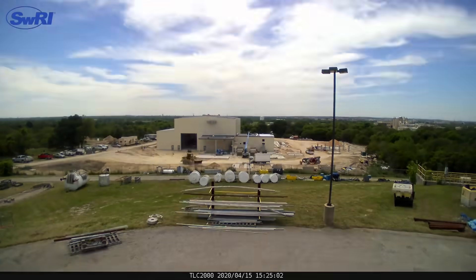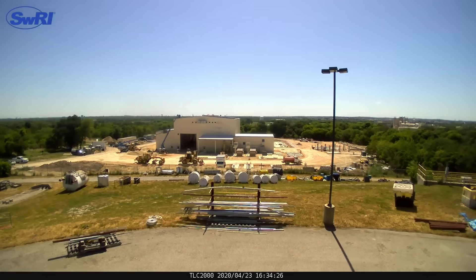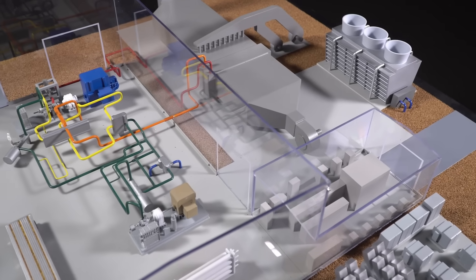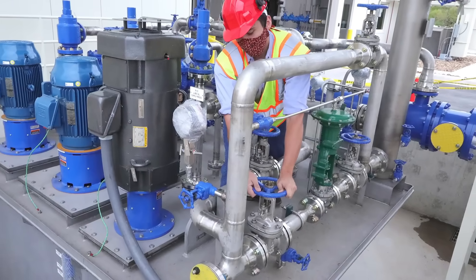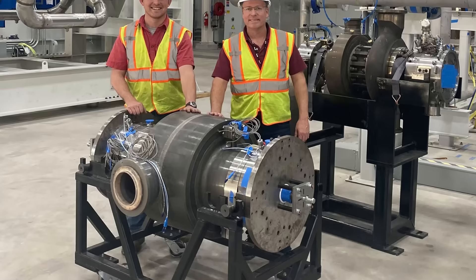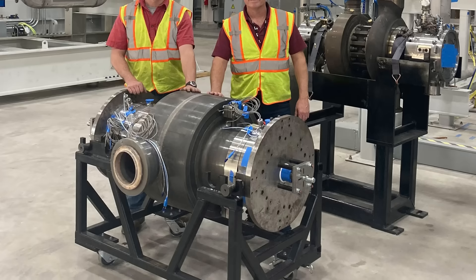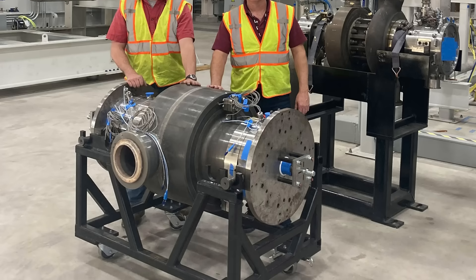The recent reveal of a pilot plant is a very good step forward for power generation. This was a collaboration project involving Southwest Research, GTI Energy, and GE. The 10 megawatt unit is considerably smaller with a 10 percent efficiency gain. It can run from a variety of heat sources and has a four-stage rotor assembly. The overall rotor weighs 62 kg, making the turbine one of the highest power density ratios — second only to rocket engine turbopumps. The casing was made from a nickel-chromium super alloy, which exhibits high strength with highly corrosion-resistant properties.